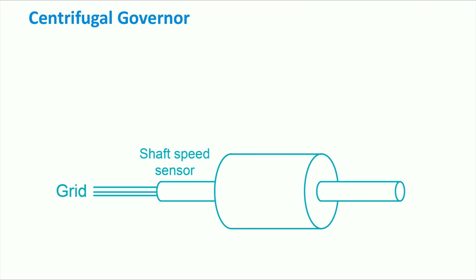The governor features a controller that monitors the rotor speed, which is tied to the grid frequency. The governor is responsible for adjusting the throttle valves of the turbine according to the speed deviations. In this way, it is possible to regulate the injection of fuel, which is gas in the case of a gas turbine, or steam in the case of steam turbines.